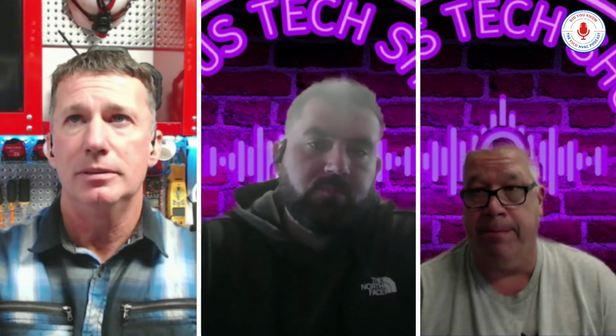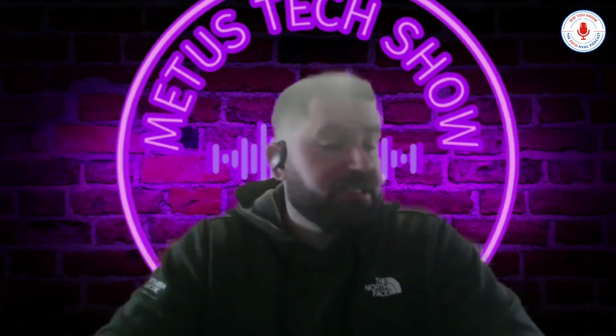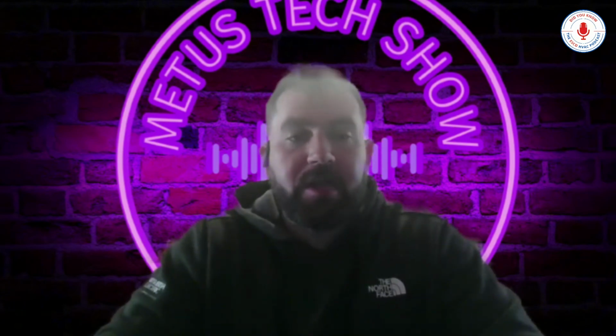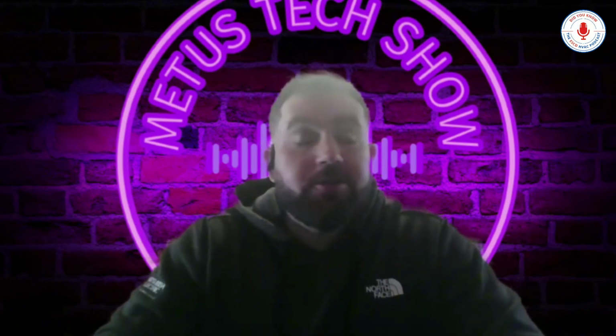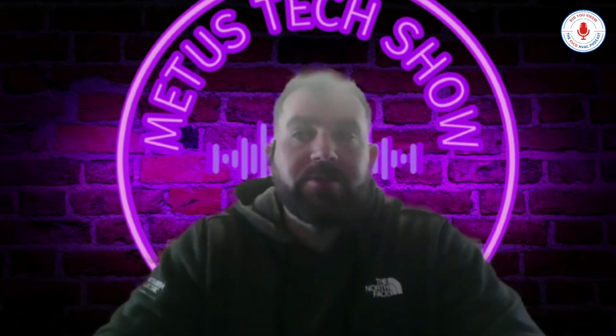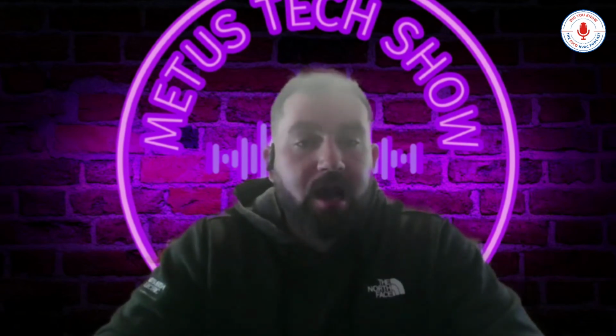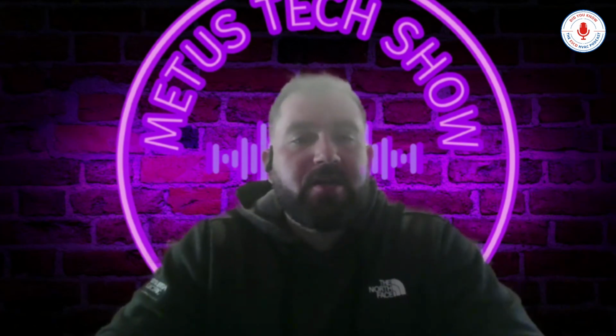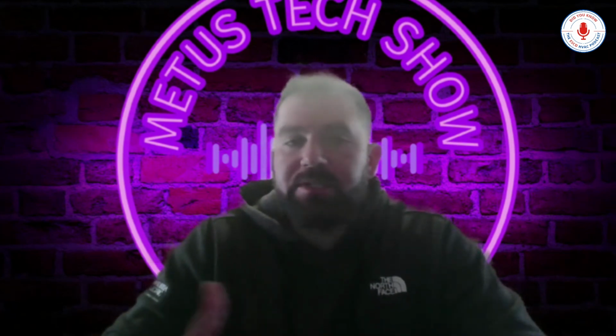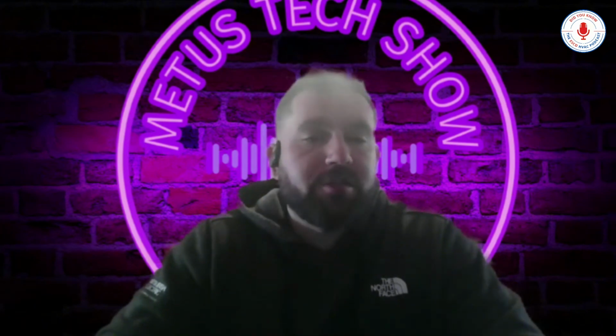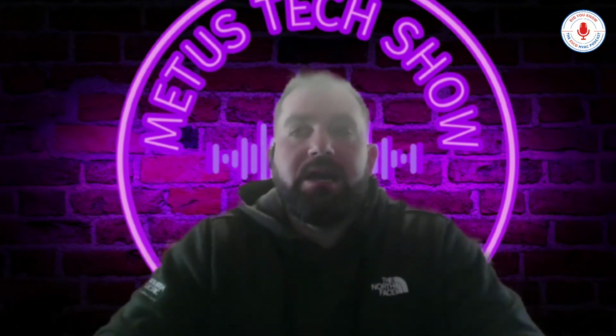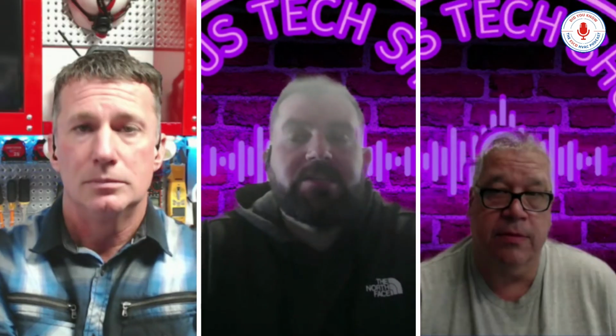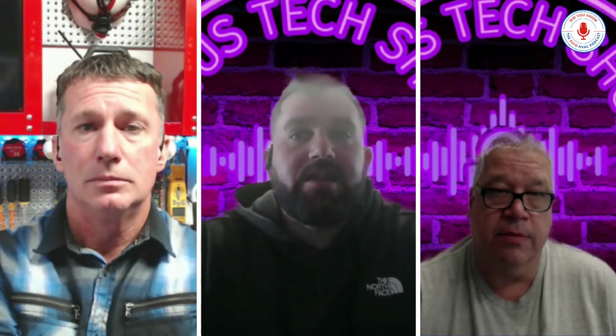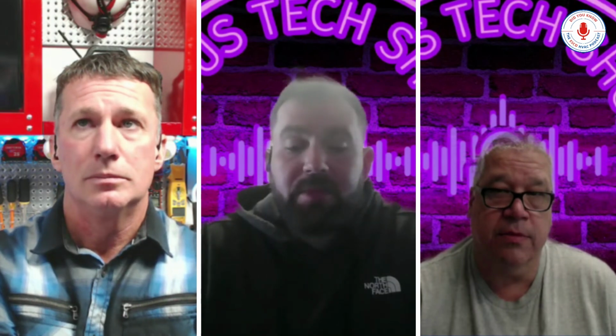Common concern, absolutely. Just speaking for myself, I was in a van only a year and a half ago, and charge related issues were typically what I was dealing with on a service call. Nowadays, with how far heat pumps have come, they're relatively reliable. It's not common to be changing components. Over 5, 10 years, you might have to replace a thermostat or a motor here and there, but by and large, they're very reliable pieces of equipment. But charge related issues were things that I dealt with on almost a daily basis. And that can be low charge or it can be overcharge.